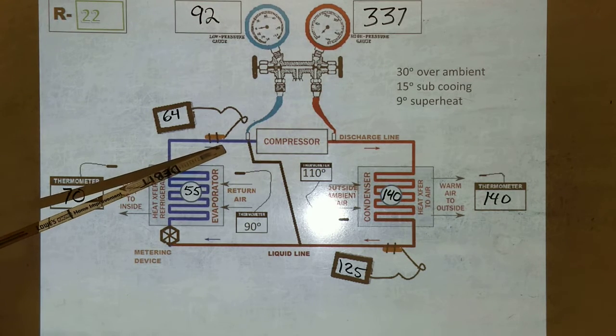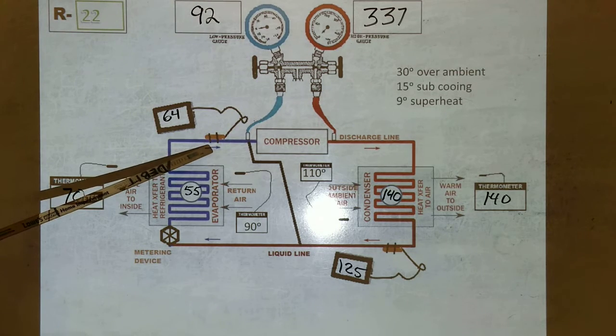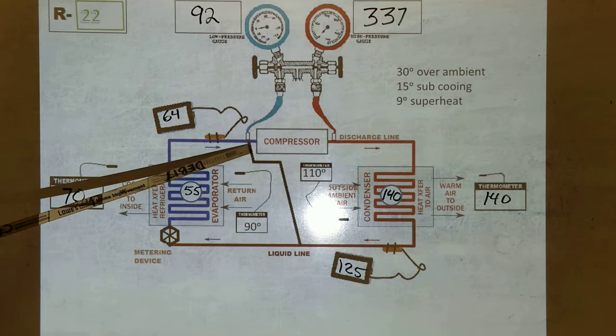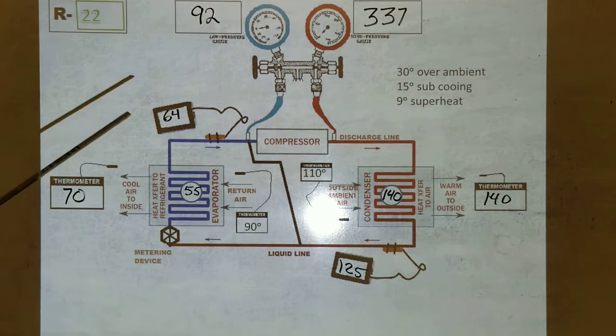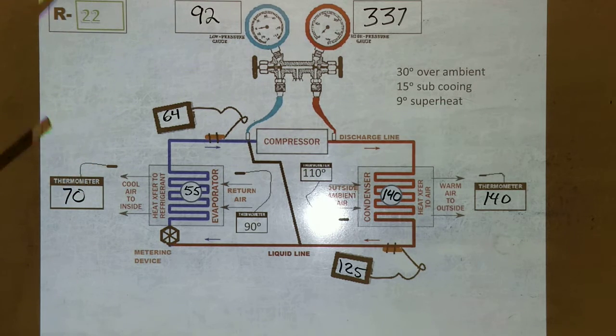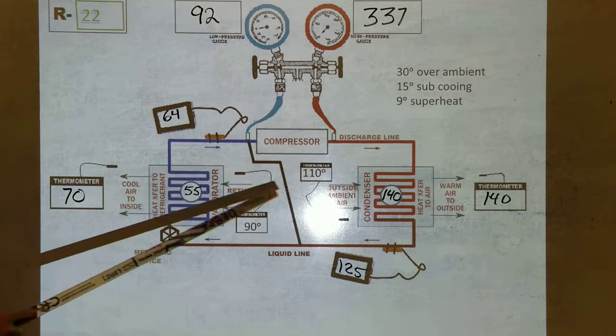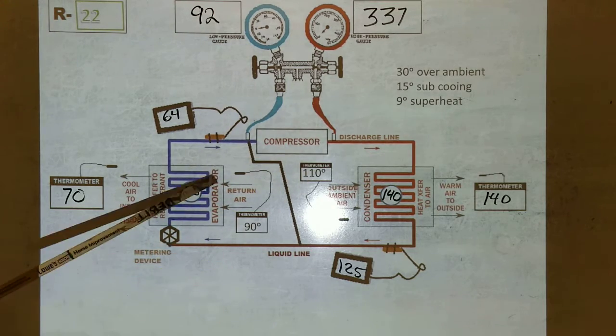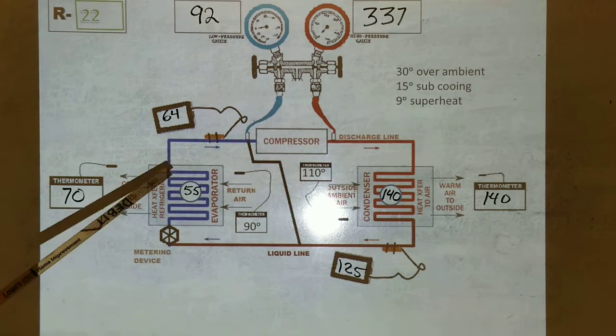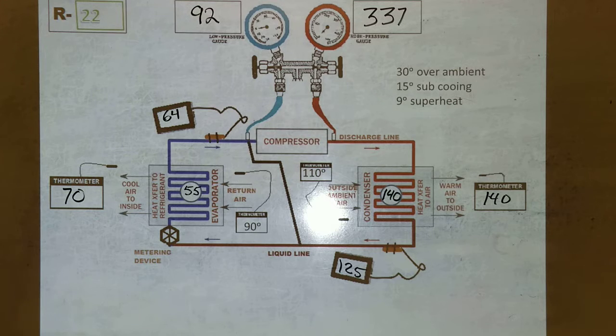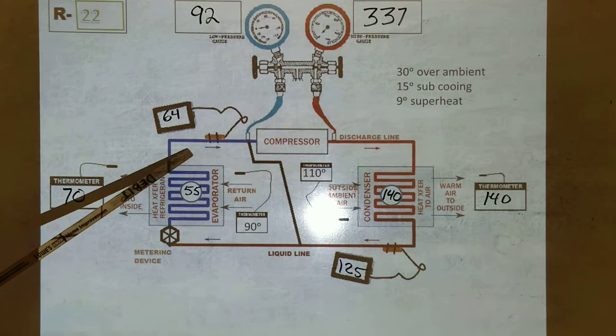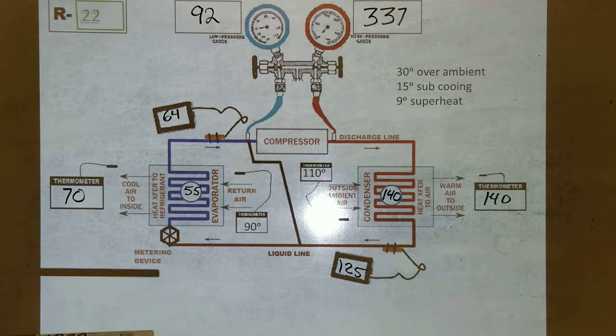Real bad. So what does that mean if we got 55 degrees right there? There's still liquid in there. Yeah, and we can't have liquid in the compressor because the compressor will only compress liquid once. And then it's not gonna do anything. It is a vapor pump. So no liquid anywhere around that compressor, none whatsoever. So we're gonna add superheat to ensure that there's only vapor going to that compressor. This is also gonna change quite a bit with the charge. If the charge is a little bit over or a little bit under, we're gonna see that on the superheat. That's the first thing that's gonna move around, so we're gonna take that temperature.